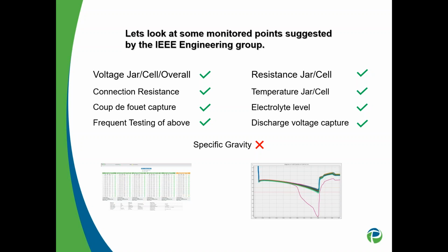Any cell or resistance, ohmic value, temperature per jar or cell, electrolyte level, discharge. If it's getting those discharge values when charging and discharging, see how the battery system responds during those conditions. Specific gravity is on there as well, but I kind of exit off because we don't provide that as far as Generex.